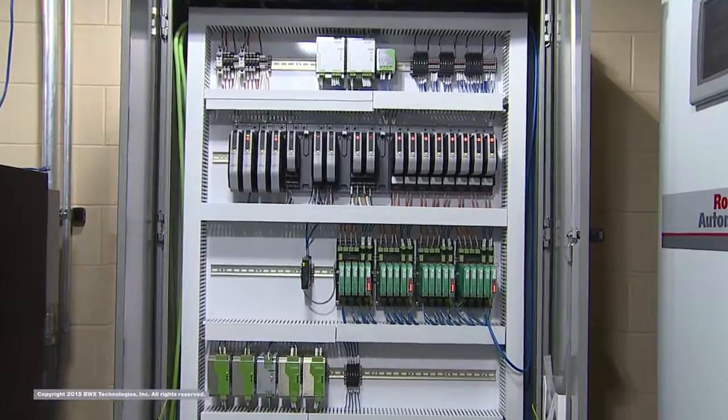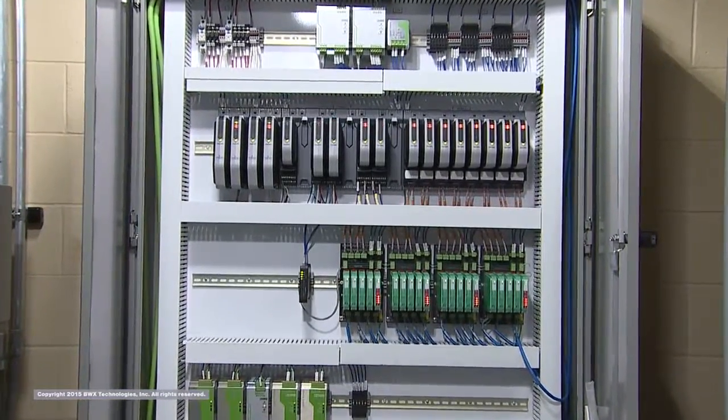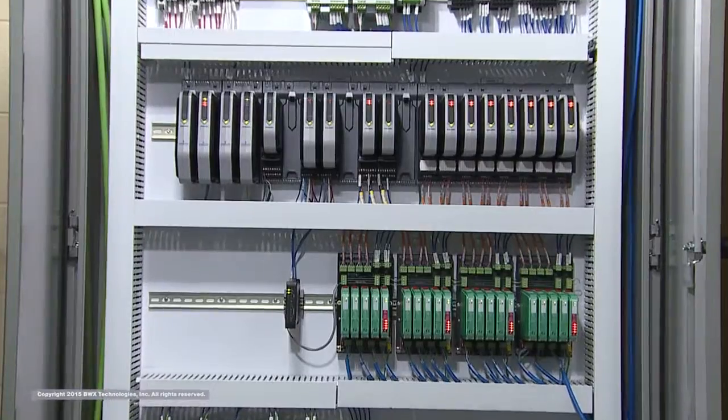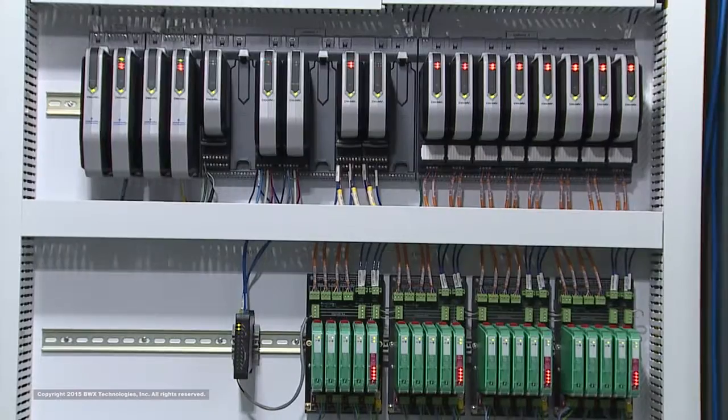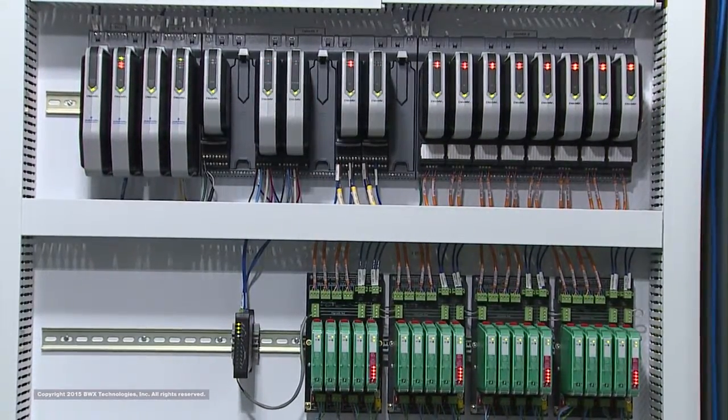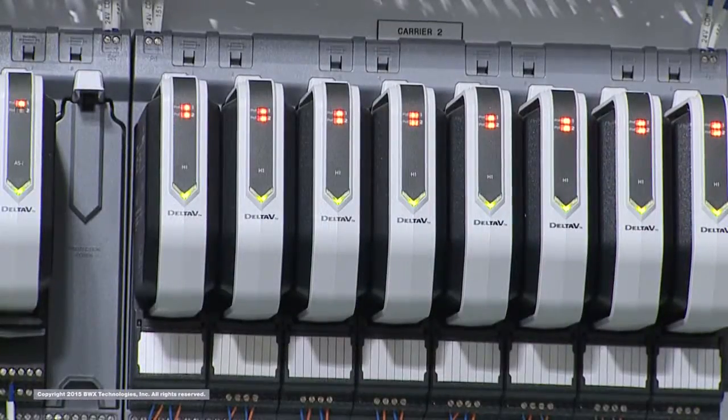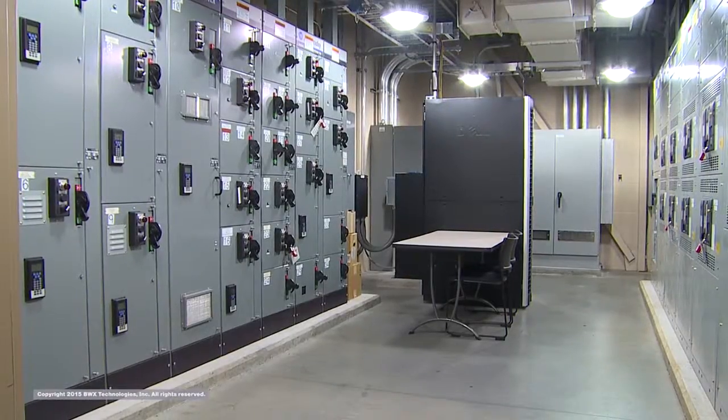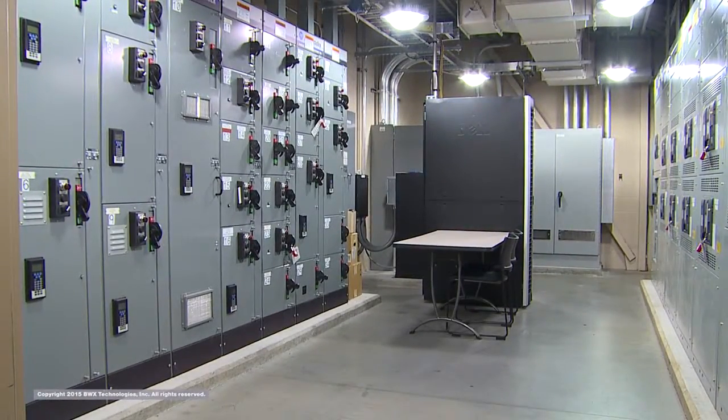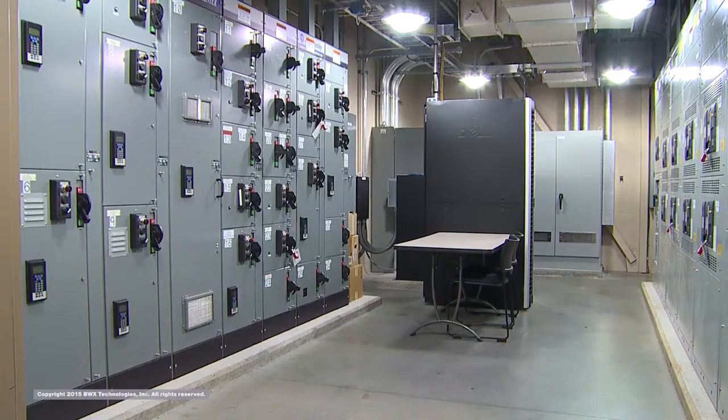Accommodation for the breadth of research and development begins with power and control requirements. The plant instrumentation and control system was designed with the latest advancements in control room technology. It includes Rosemount instrumentation, Emerson Delta V control system, 20 interactive operator control interface screens, more than 500 instruments with online continuous data collection, remote viewing of plant operation and data extraction, variable frequency drives for components increasing integrated operation, tuning, and component flexibility.